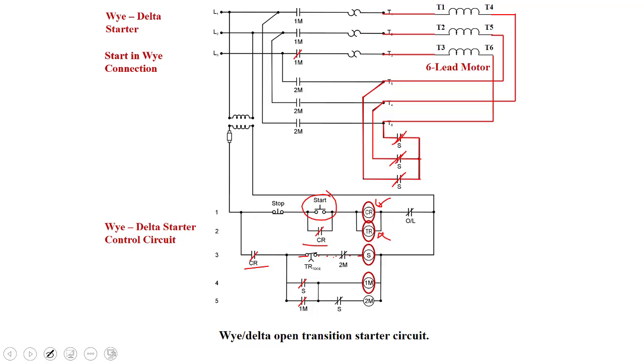When this S contact closes, it energizes 1M, so 1M contacts close. What else energizes 1M? Well, this one right here. That acts as a holding contact. And this one right here would go to an open. Whenever S is energized, that normally closed will open, so 2M is not energized right now. If we follow our diagram here, line 1 goes through 1M, goes to T1, and through T1 to the T4 coil. It comes in, and the motor right now, it's the same on each one of them. It is connected in star or Y.